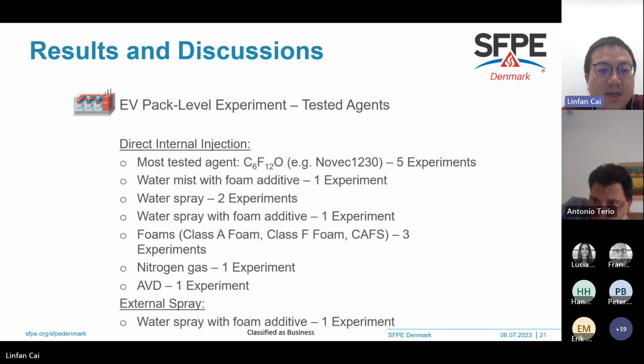The tested agents in the EV pack level experiment show Novec gas as the most tested agent. A possible reason is the space limitation in electric vehicles: water-based agents require more space than gas-based agents, so Novec gas has been mostly tested. The rest, like water mist, only have one or two experiments, and nitrogen also has just one experiment, probably because researchers already knew Novec gas would have a better cooling effect than nitrogen inert gas.